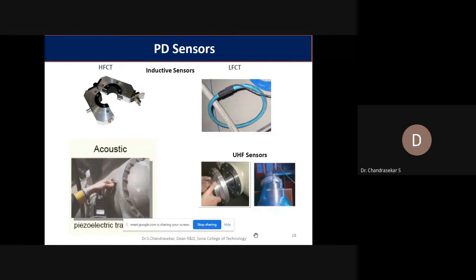So these are the high voltage sensors available. HFCT and LFCT are inductive type sensors: HFCT means high frequency current transformer, and LFCT means low frequency current transformer. Based on the piezoelectric principle, acoustic sensors are also developed. Then there are UHF sensors, ultra high frequency sensors, and TEV sensors, transient earth voltage sensors. There are so many sensors developed for understanding the discharges or leakage currents happening in high voltage systems. We will see them one by one.